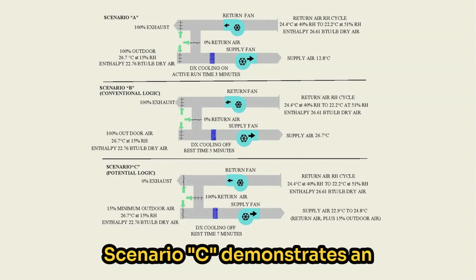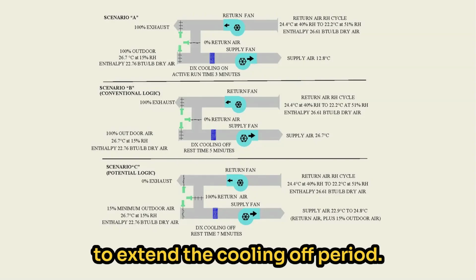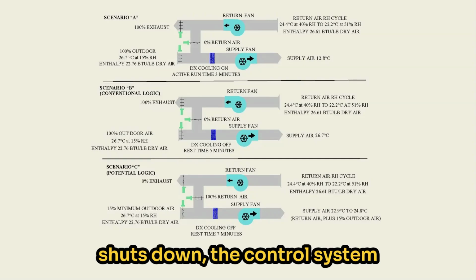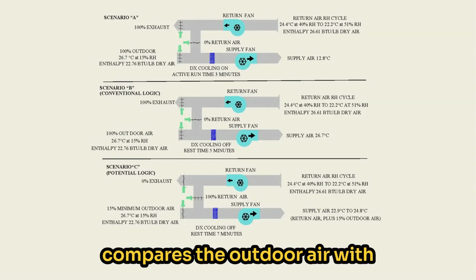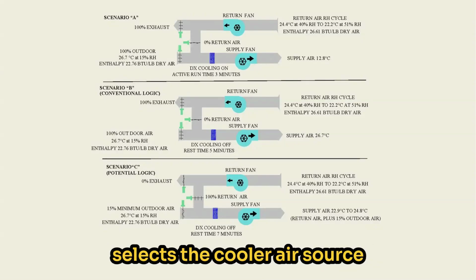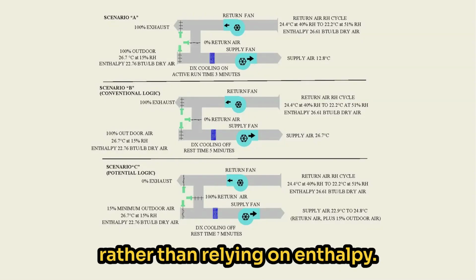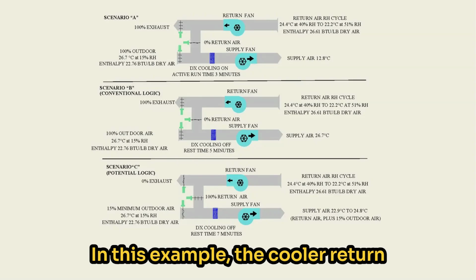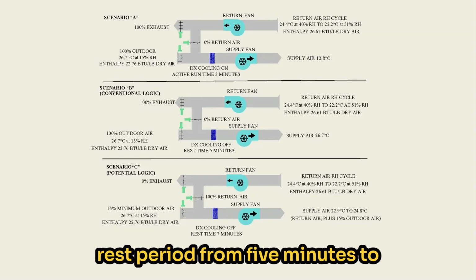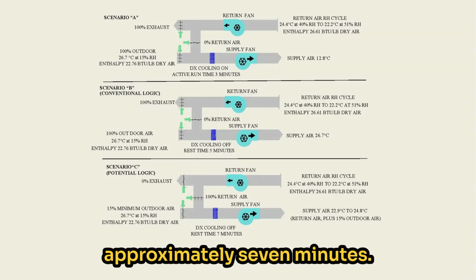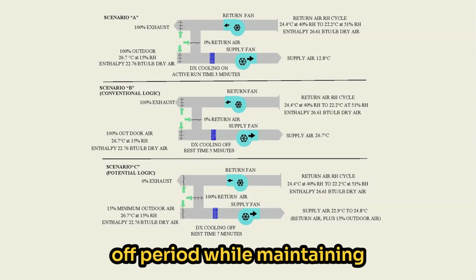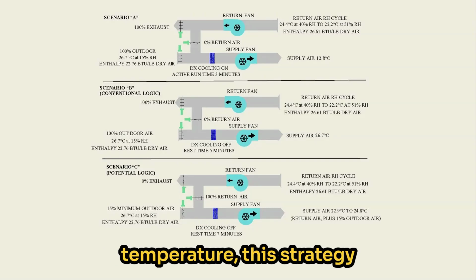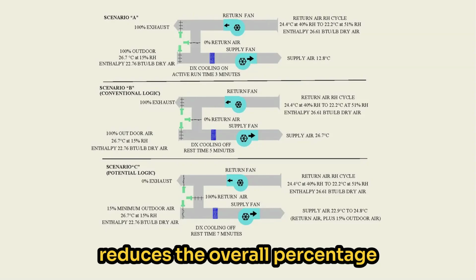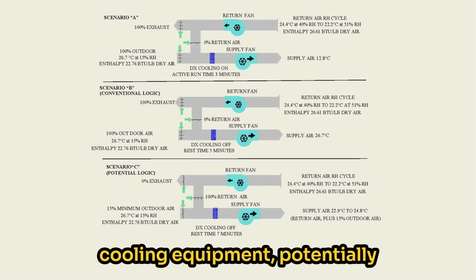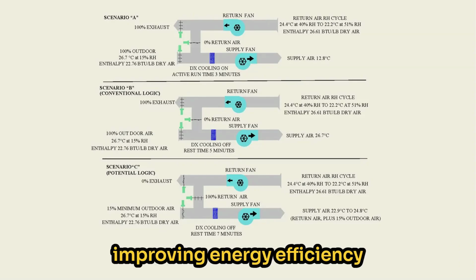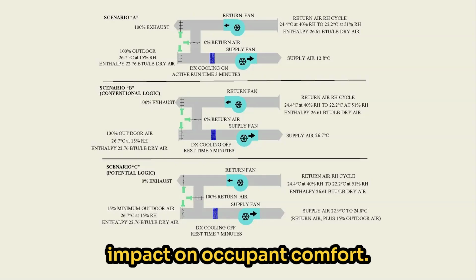Scenario C demonstrates an alternative approach intended to extend the cooling off period. When mechanical cooling shuts down, the control system compares the outdoor air with the return air temperature and selects the cooler air source rather than relying on enthalpy. In this example, the cooler return air is used, extending the cooling rest period from 5 minutes to approximately 7 minutes. By increasing the cooling off period while maintaining the same occupied space temperature, this strategy reduces the overall percentage of runtime of the mechanical cooling equipment, potentially improving energy efficiency with little or no noticeable impact on occupant comfort.